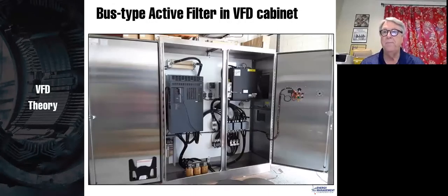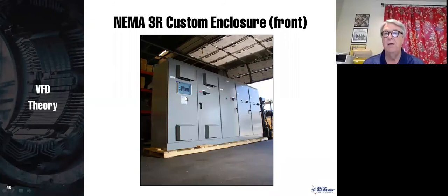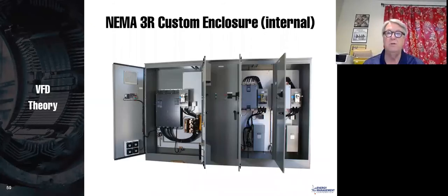And this one is a drive that has an active filter, not an active front end, but an active filter. And we went ahead, because this is, I guess, convenience for mounting, and put the active filter actually inside the drive cabinet. So that's an active filter, and over here is the drive. There's a NEMA 3R custom enclosure. Here's one with a drive and 2 soft starts.